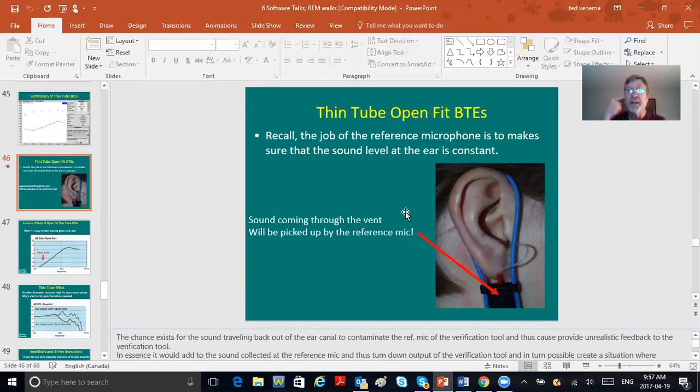Always remember that. If you're wearing the real ear system, loop around the ear, and you move closer to the speaker, it will reduce its volume in order to maintain the sound that you wanted it to put out. 55, 65, 75, whatever. If you back up, the sound from the speaker will get louder to maintain the level that you suggested for it, okay? So that's what the reference mic is doing. Test that on yourselves on a real ear system sometime. Hang that loop around, get it going with its stimulus, and move back and forth and listen to the effect of what the reference mic is doing.